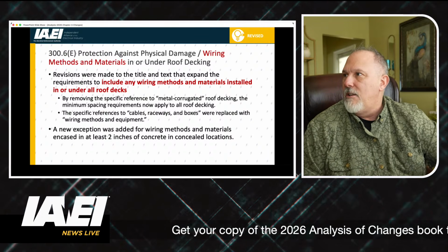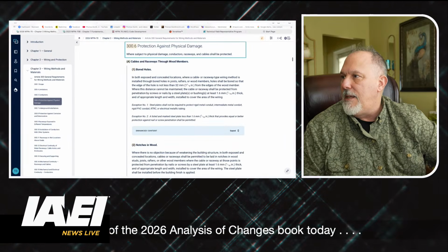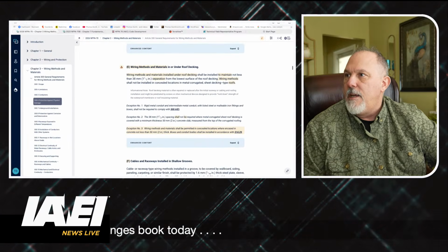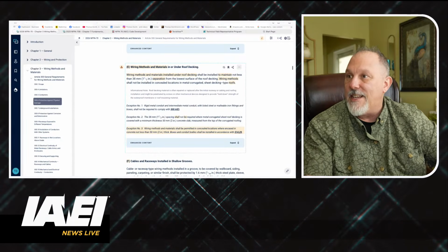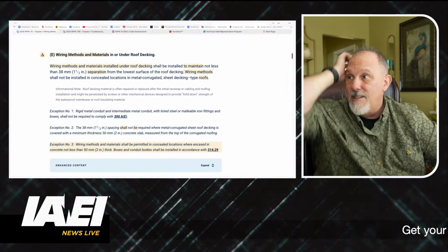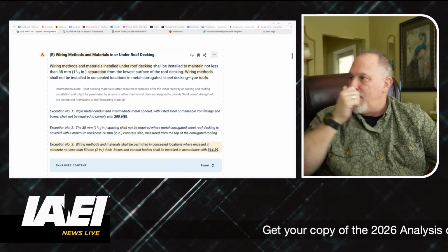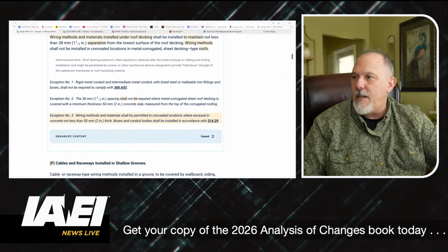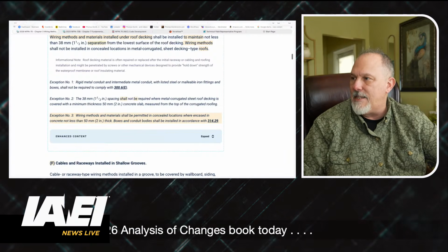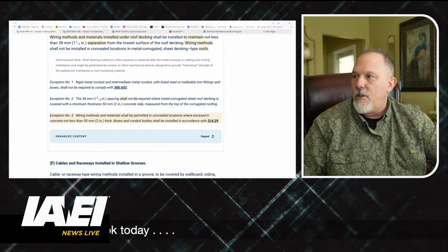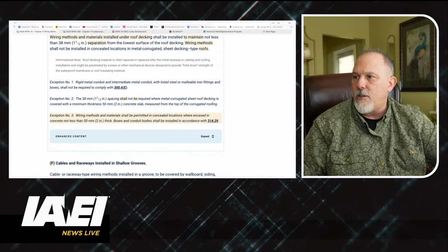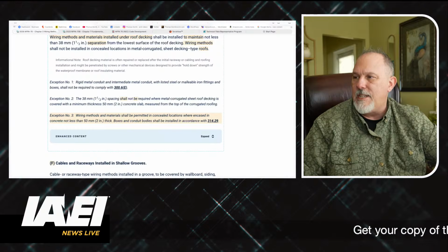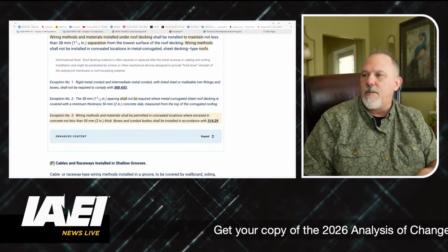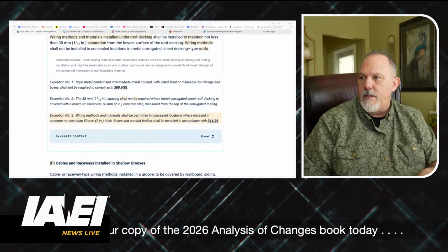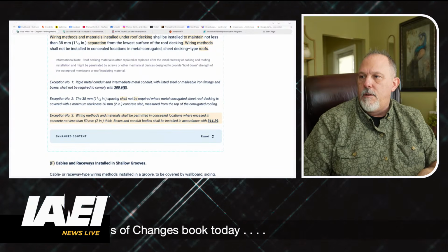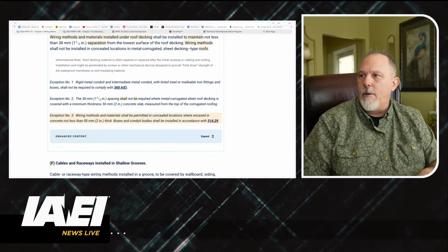I don't know. Let's take a look at 300.6(E), because I'm wondering if it says concrete, because there could be other wiring methods and materials. Wiring methods and materials shall be permitted in concealed locations where encased in concrete not less than 2 inches thick. Boxes and conduit bodies shall be installed in accordance with 314.29. Wiring methods and materials shall be permitted where encased.